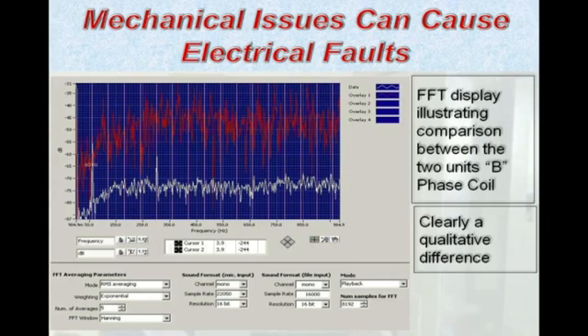And this is a 60 hertz system for our friends overseas, so I have the harmonic cursor set to 60 hertz. And we see some activity present with the red trace, the suspect coil, compared to the sister unit, which is a lot quieter or lacking in activity compared to the red trace.